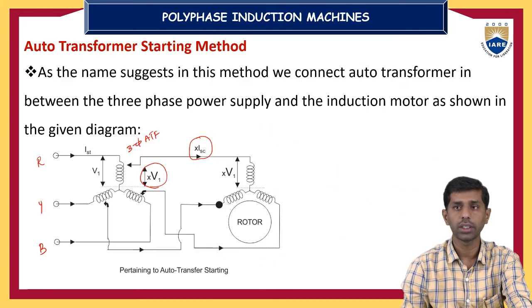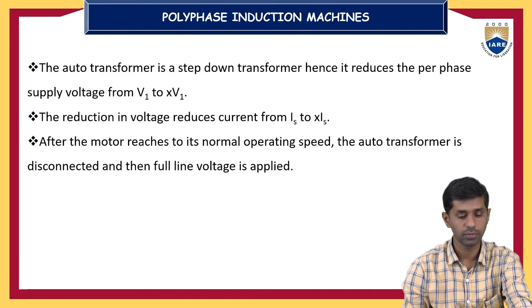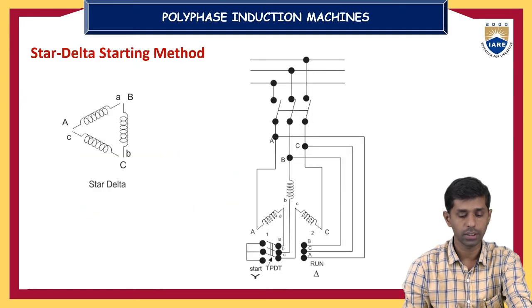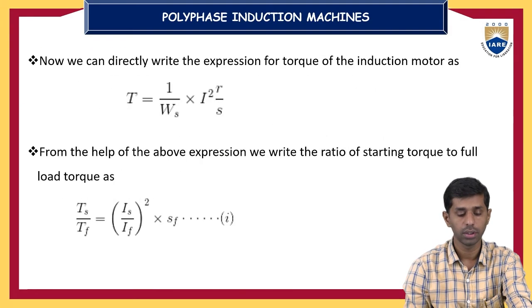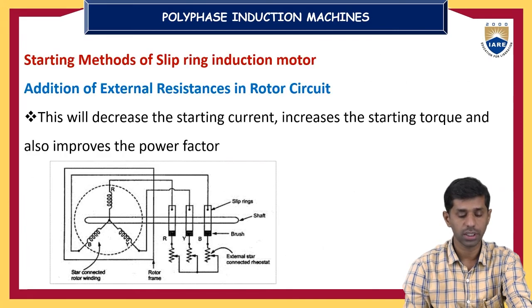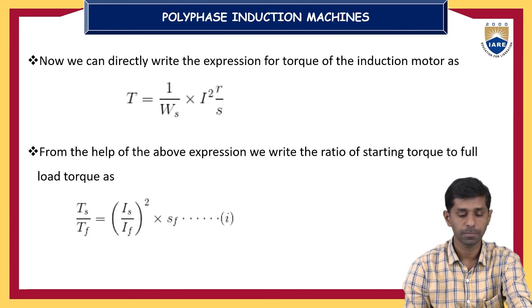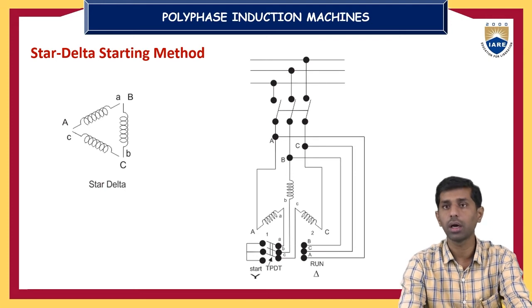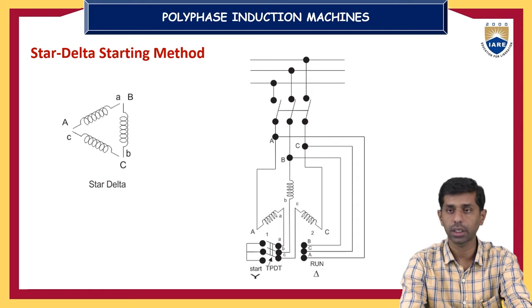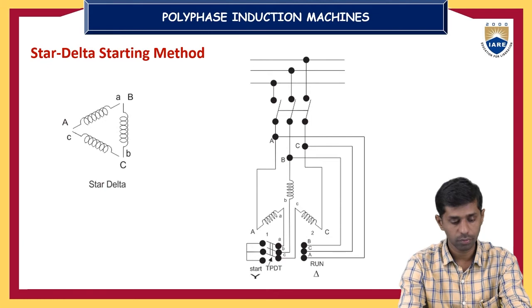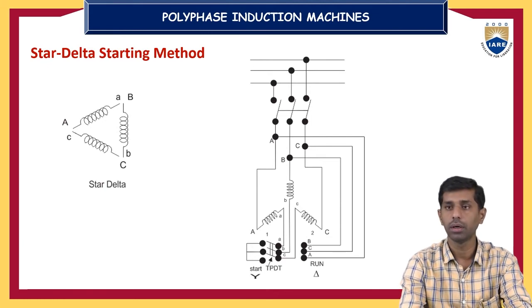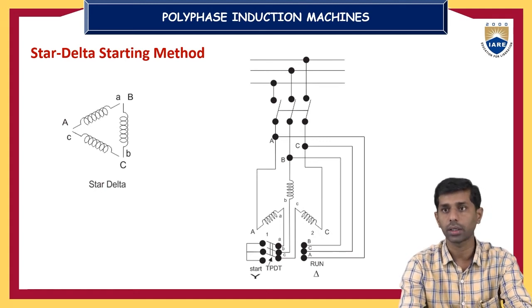So in the reduced voltage starting methods, we have finished two types. One is the stator resistor starting method, and the other is the auto transformer starting method. The next method is the star delta starting method for squirrel cage induction motor. From the name itself, we will understand what kind of method it is and how we connect the stator winding at the time of starting and at the time of running.